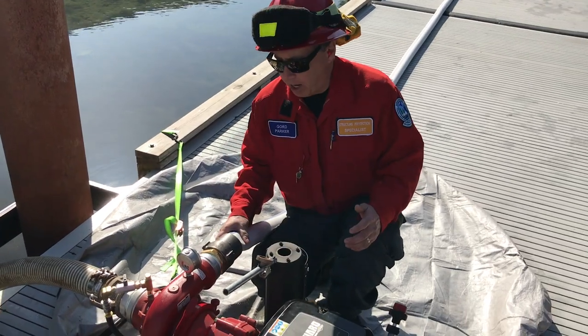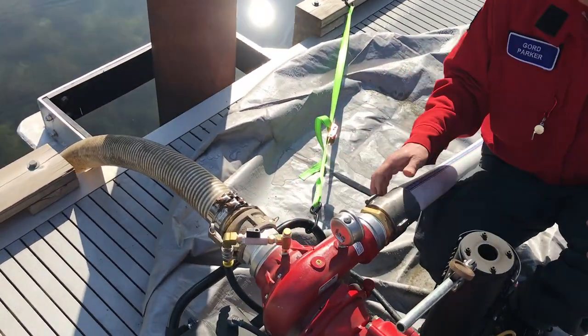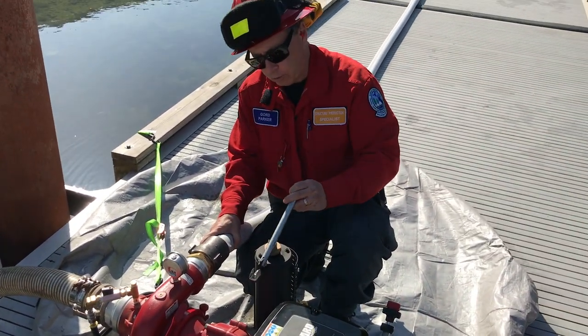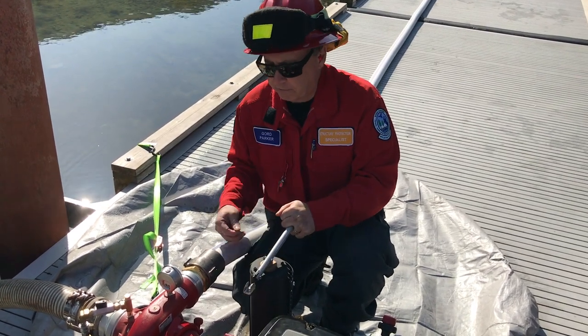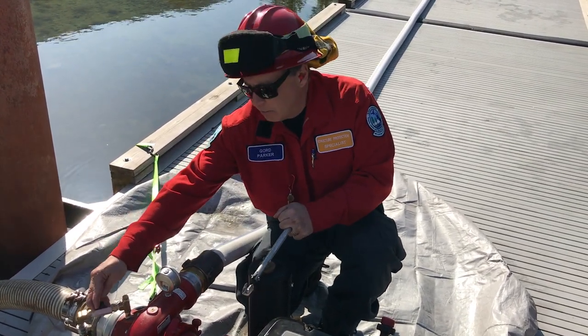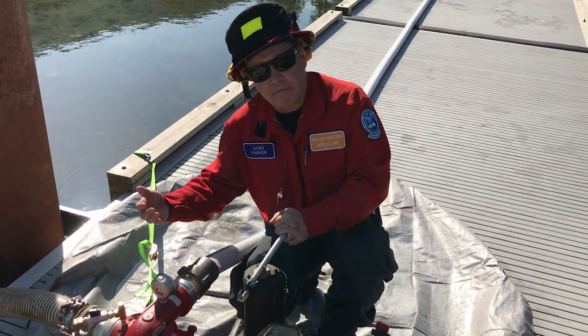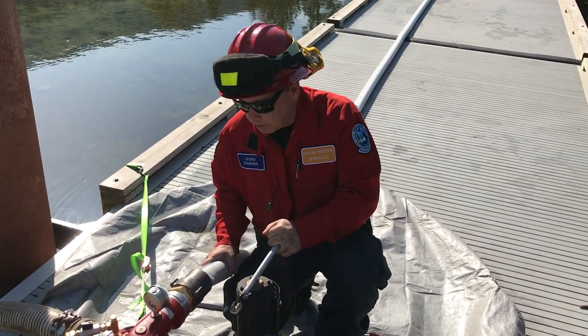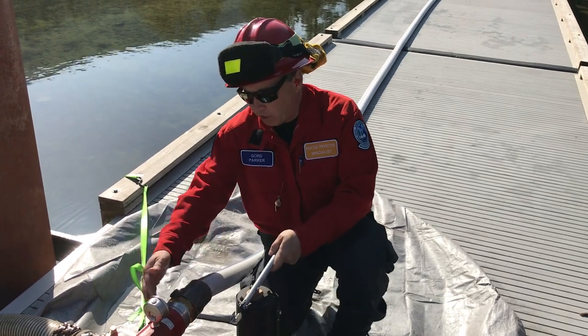So when we're ready to prime, we open the priming valve. And then we're going to close the top of the exhaust port. What it's going to do now is divert exhaust gases past the valve into the pump casing, and it's going to create a venturi effect where it's going to start to draw water up from the suction hose.